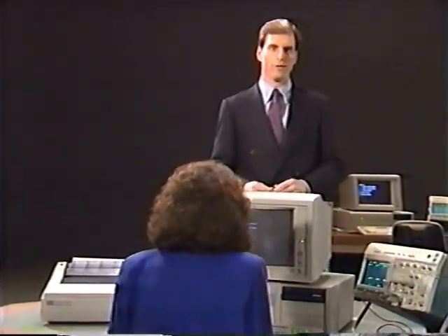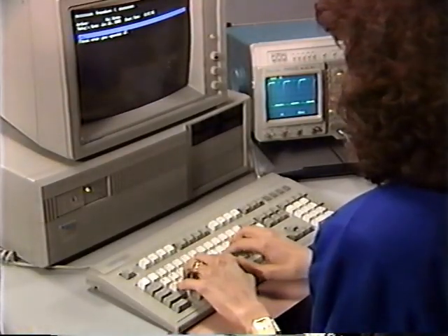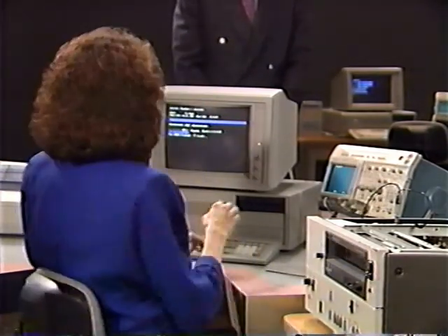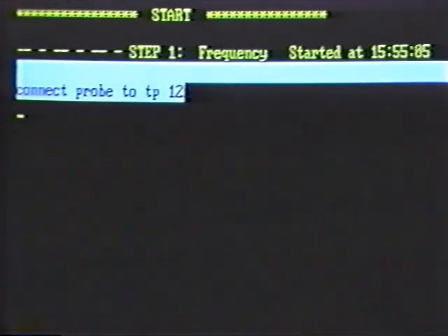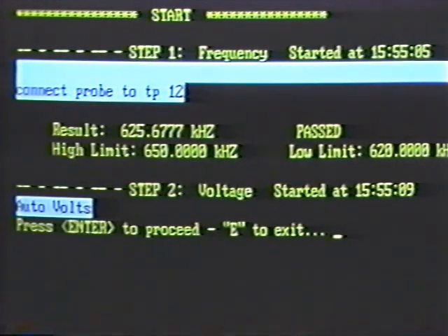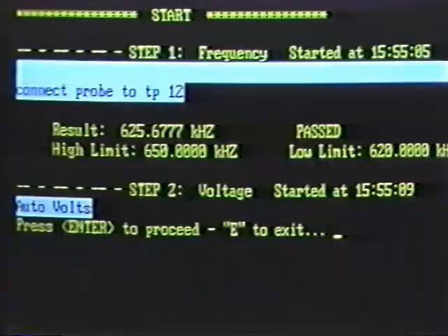After calling up the procedure, enter your name and follow instructions. The prompt message guides you to the test point and explains what to do. We've connected our probe to test point 12, and the scope measures the frequency. The results are displayed on the screen. The controls for the 2465A are automatically set up for the measurement. The measurement result is tested against limits, and then a pass or no pass decision is made, just as you see here. In this case, pass is indicated, so we'll proceed with the next step. If it had failed, the software would branch to a troubleshooting procedure, then return to the mainstream of the program.